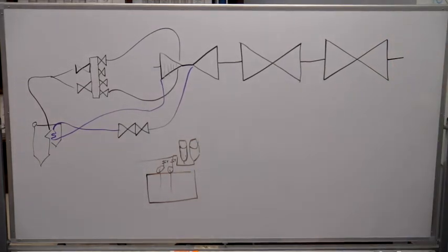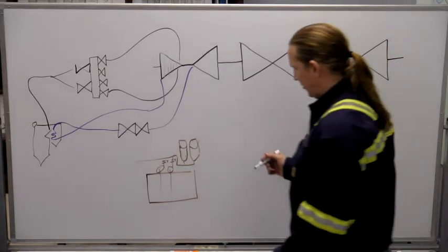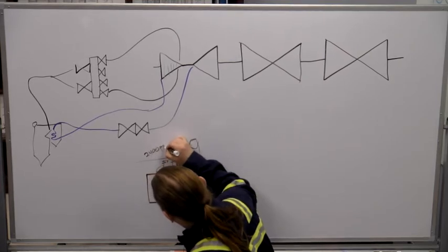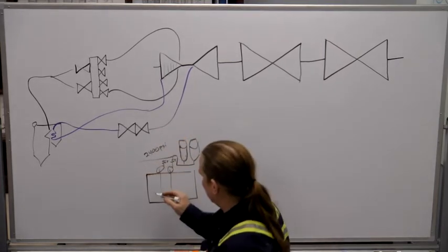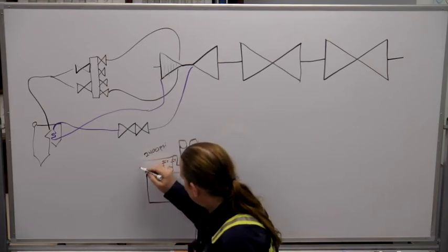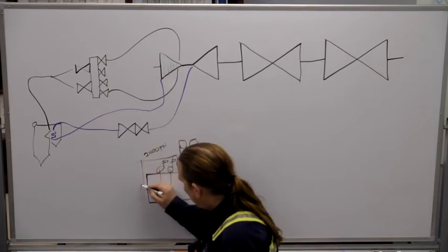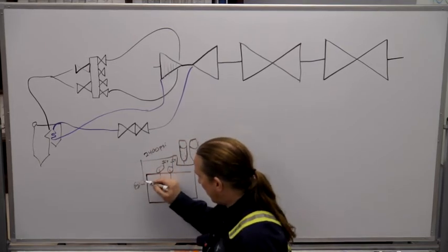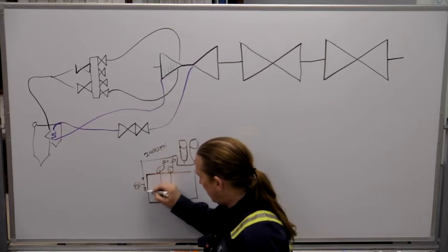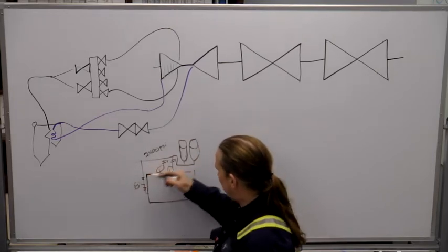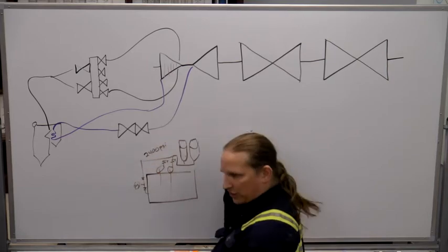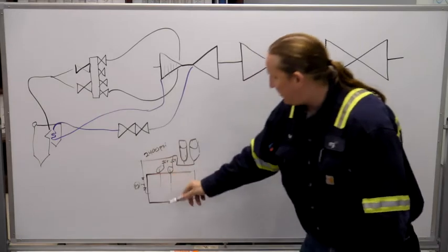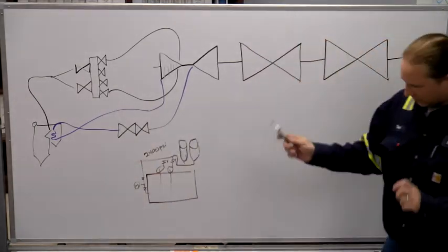The system operates at 2,400 pounds. There's a pressure switch, and there's a weekly test where we isolate the accumulator and vent off the pressure. When it drops below 1,700 pounds, it starts the standby pump — test good. Then we align the switch back up and swap pumps every week.